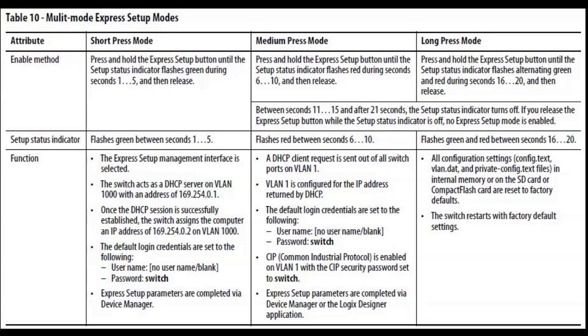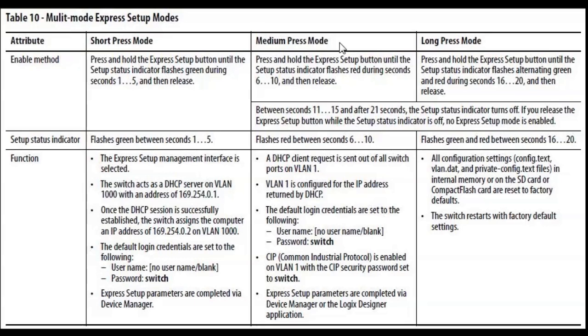There are three modes to the express setup for the Stratix managed switches. The short press mode is what we're going through today, where the switch will assign an IP address to our computer. The medium press mode would be if you have a DHCP server, or in some cases we've used BootP. If you prefer to use the BootP method, you can use this.